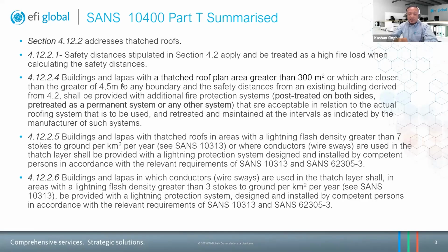Problem is, any other system needs to be designed by a fire engineer. And again, that will involve a rational design. I'm not going to jump into that right now. Buildings and LAPAs with a thatched roof in areas with a lightning flash density greater than 7 strokes to ground per square kilometer per year, and that's according to SANS 10313, or where conductors or wire sways are used in the thatched layer, shall be provided with a lightning protection system designed and installed by a competent person in accordance with the relevant standards. Now, if you do have those wire sways and they are used in the thatch layer, they also shall have lightning protection systems installed.